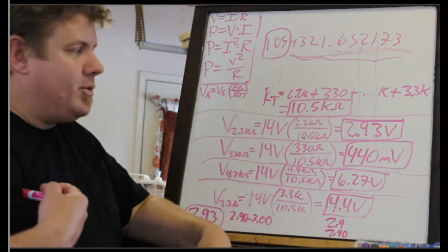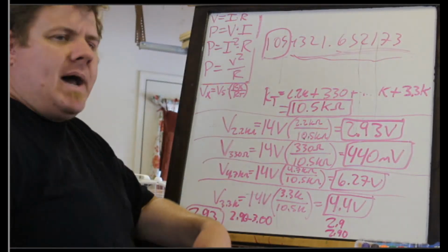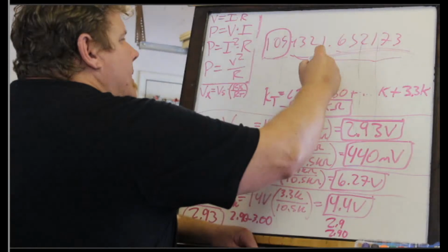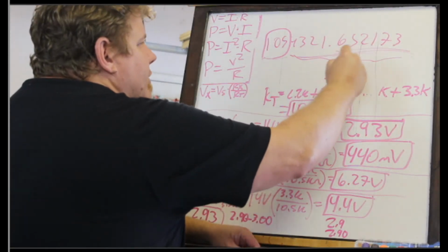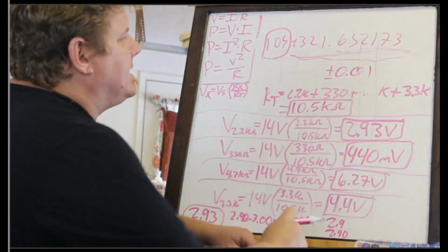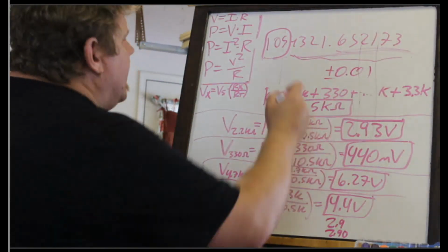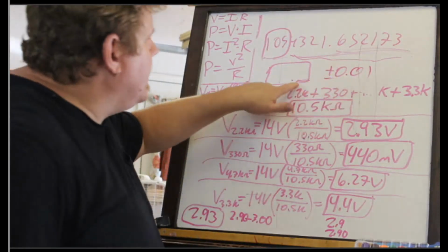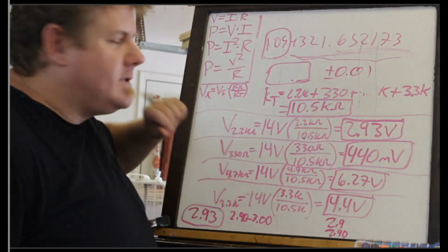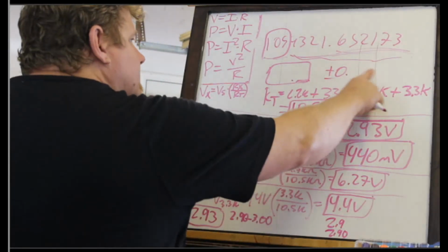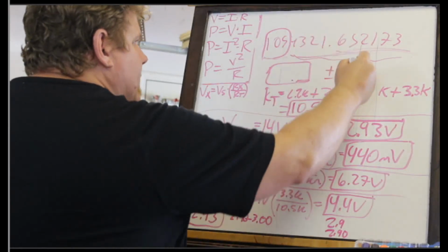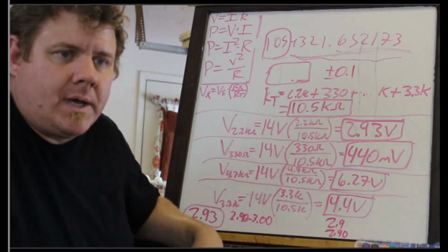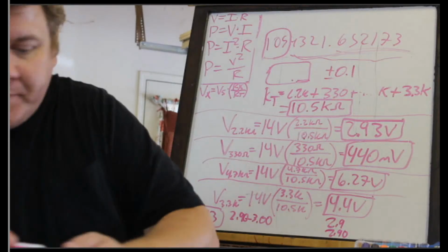Even when I was in calibration and metrology, it always killed me when a device had an accuracy of, let's say, in one range plus or minus 0.01, let's say. So that's the accuracy of the device. And the display only does 1 digit. How can you give me that accuracy if you're only going to display one of the digits? It's against the rules. Whatever the resolution is, it's going to dominate whether what your accuracy is or not. And so, the best that you could do with a resolution like that is 0.1. Okay. So anyway, any other questions?